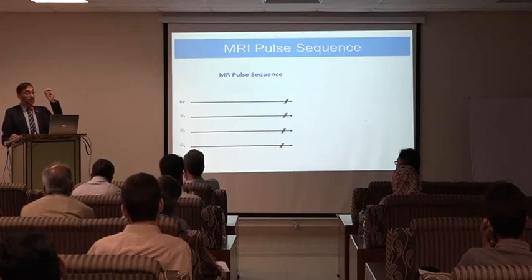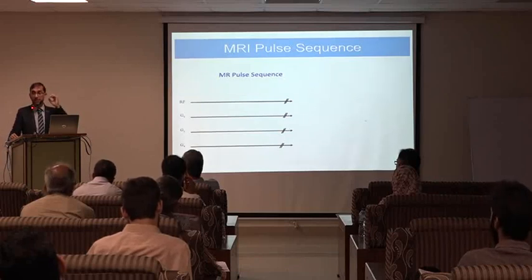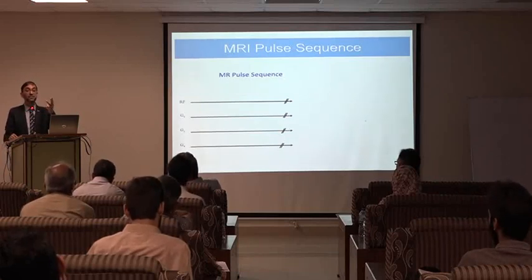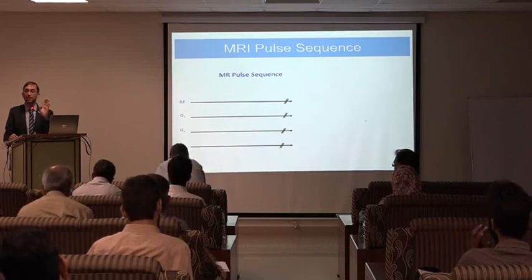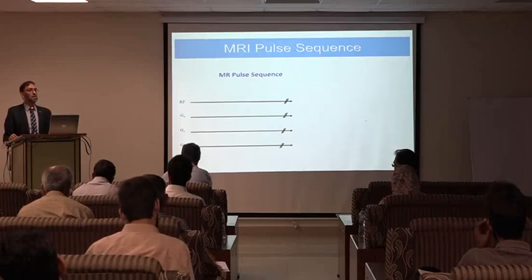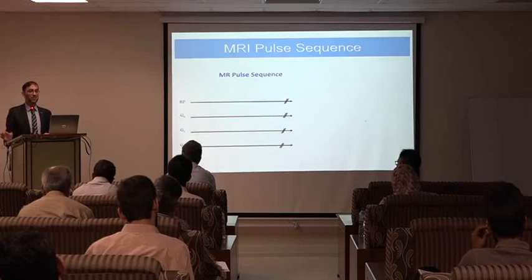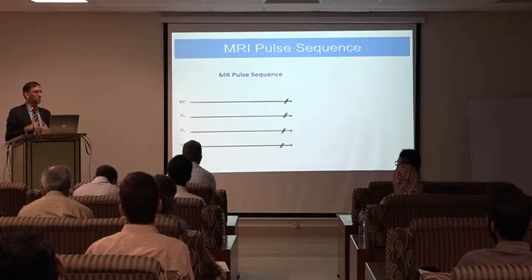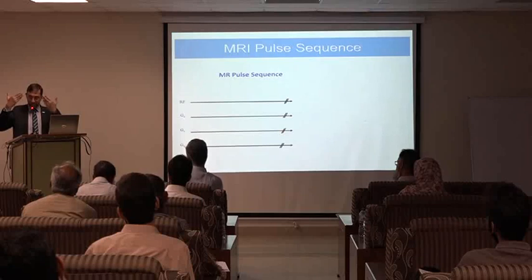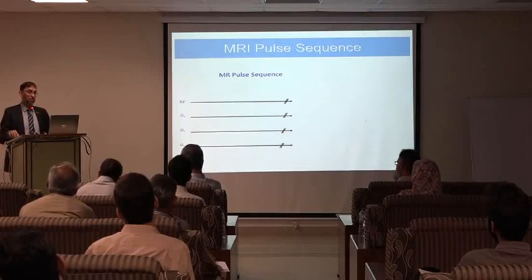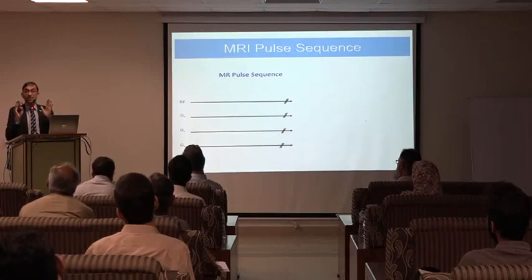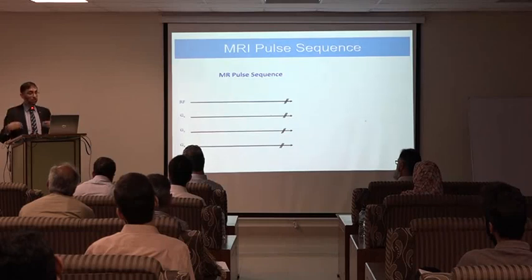It's not only the permanent magnetic field, it's also the 3 gradient fields. The permanent magnet produces a magnetic field strength measured in Teslas, but the gradient fields produce a magnetic field strength of milliteslas per centimeter. It's about 1,000 times smaller, because you have to produce slight variations depending upon the parts of the body you want to image. So it's the 3 gradient fields which produce that variation, so that the resonance frequency changes across the parts of the body.